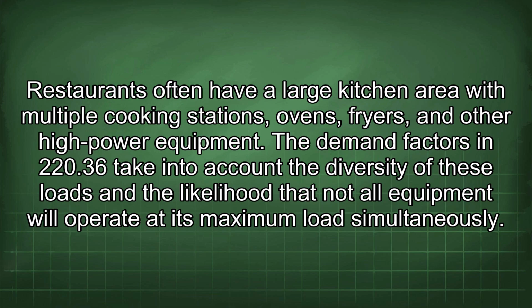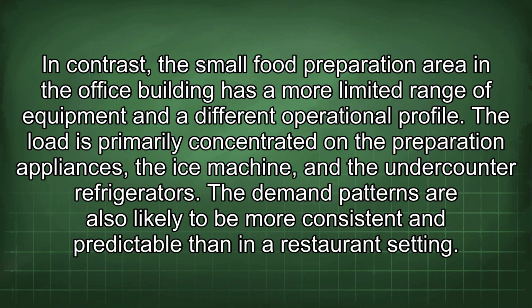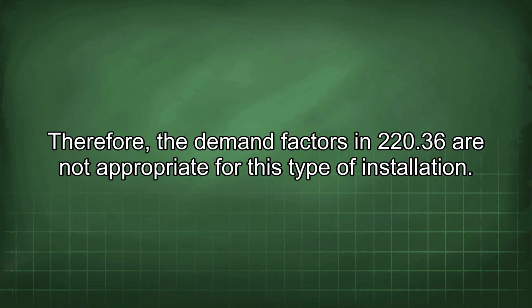The demand factors in 220.36 take into account the diversity of these loads and the likelihood that not all equipment will operate at its maximum load simultaneously. In contrast, the small food preparation area in the office building has a more limited range of equipment and a different operational profile. The load is primarily concentrated on the preparation appliances, the ice machine, and the under-counter refrigerators. The demand patterns are also likely to be more consistent and predictable than in a restaurant setting. Therefore, the demand factors in 220.36 are not appropriate for this type of installation.